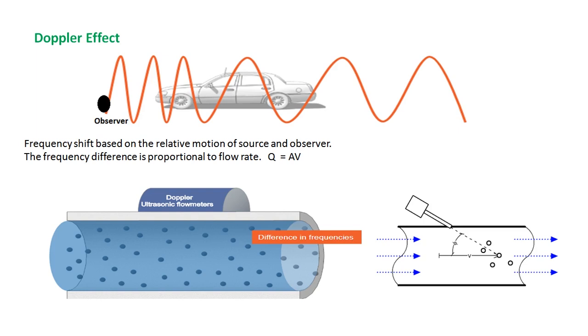The ultrasound is focused onto the liquid, which contains some bubbles or particles that act as the observer. The reflected frequency is then measured by the source. Since flow rate equals the cross-sectional area of the pipe multiplied by velocity, and the area is known, putting in this velocity gives us the volumetric flow rate.